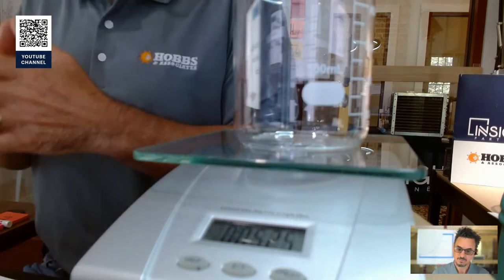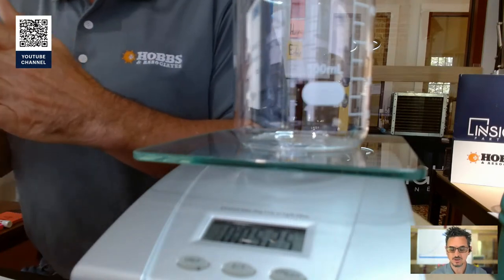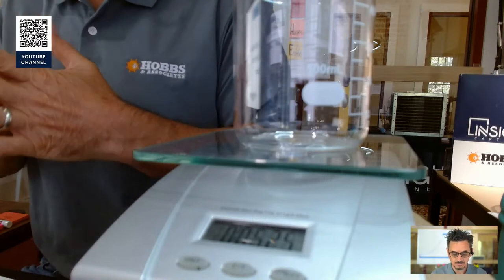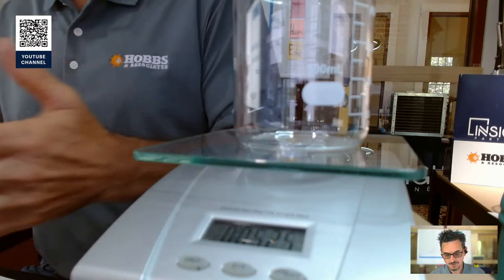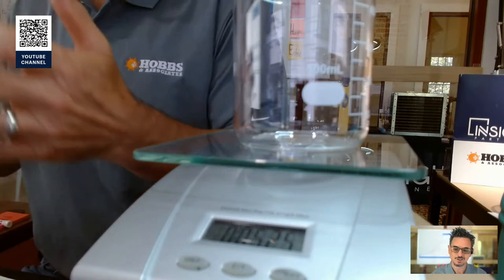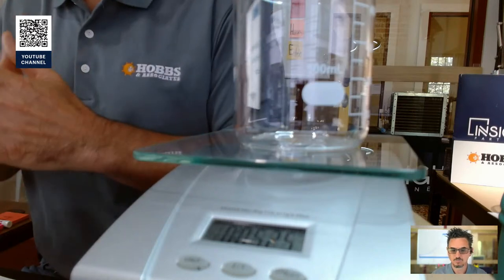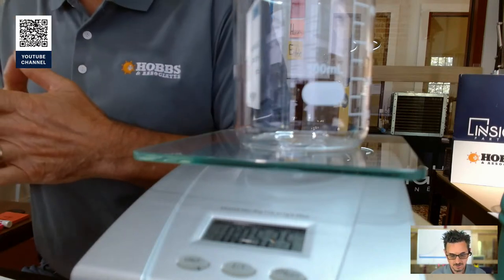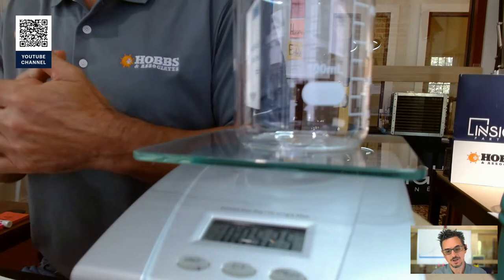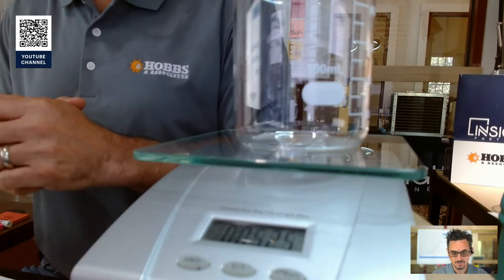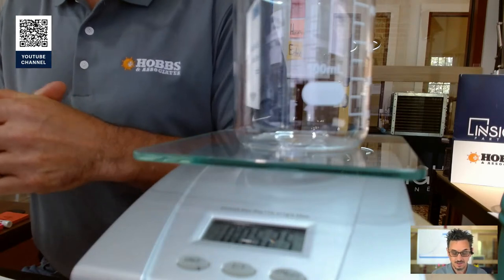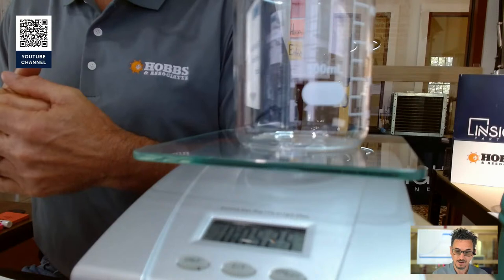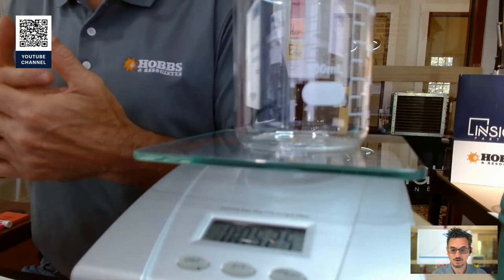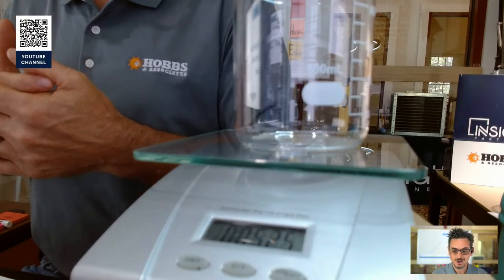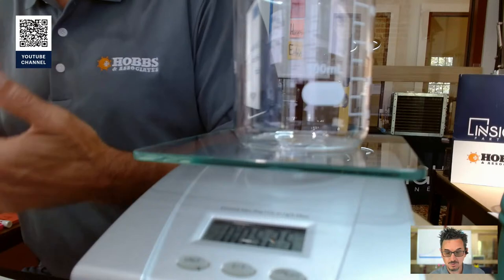At standard-ish conditions, a pound of air is about 14 cubic feet of air, which is, if you envision a cube about 2.5 feet length, width, and height, approximately 14 cubic feet of air. On a 95-78 day, which is an extremely hot and humid day, that is equal to 120 grains. So what does 120 grains of water look like? Well, it's equal to about 8 grams.